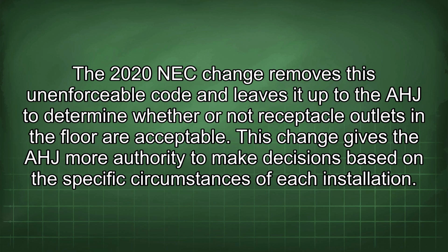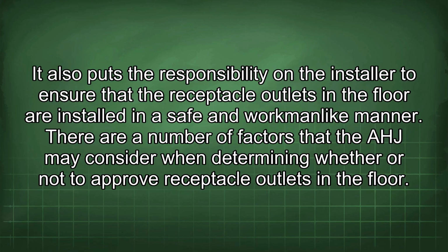This change gives the AHJ more authority to make decisions based on the specific circumstances of each installation. It also puts the responsibility on the installer to ensure that the receptacle outlets in the floor are installed in a safe and workmanlike manner.